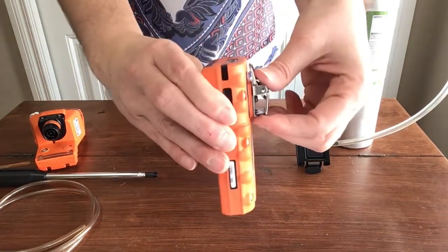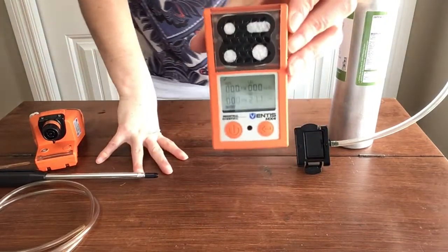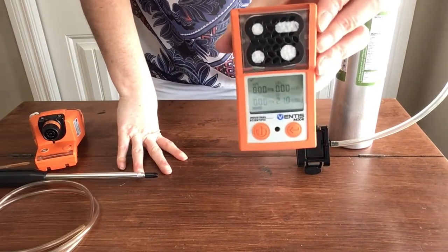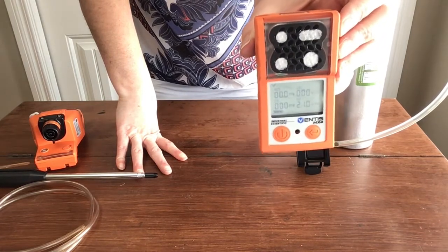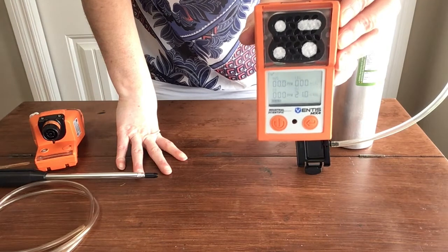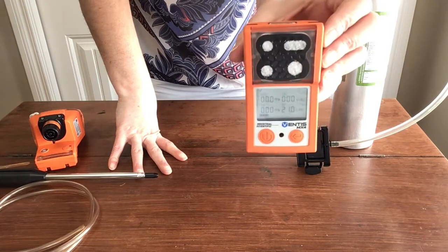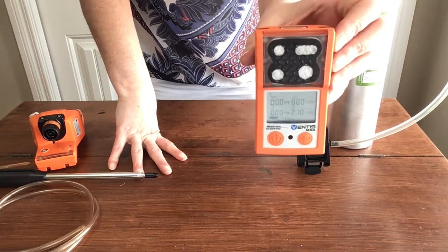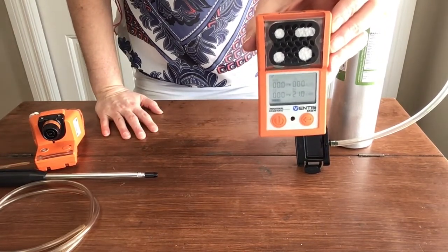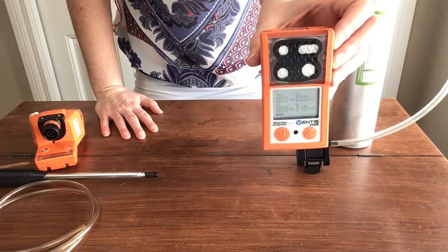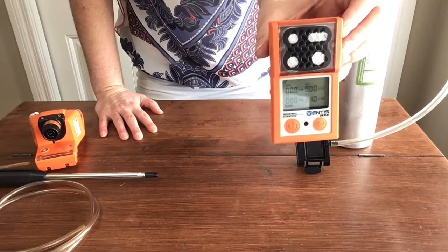They're going to make sure that they clip it using this clip here in their breathing zone, okay? So this should not be clipped on a belt, on a tool belt or anything of that nature. It should be clipped at their breathing zone. Sometimes you'll hear workers say that they clip it down nearer to their feet if they're working with a gas that's heavier. And while I understand that, typically we want it in the breathing zone so that as soon as any gas gets into the area where you're going to be breathing it, you'll have indication of that right away. And oftentimes when you're working in a specific space, there's not only one hazard. And so having it in the breathing zone is just the best placement for all of the hazards that are present, okay?